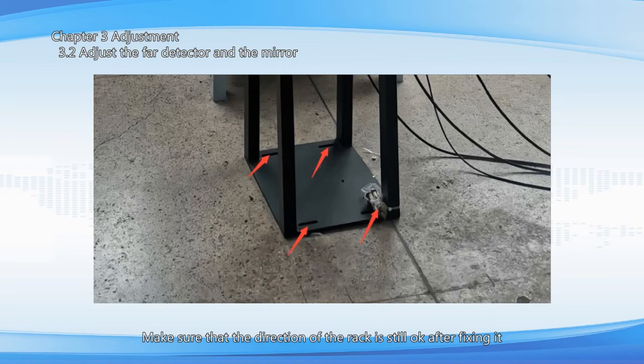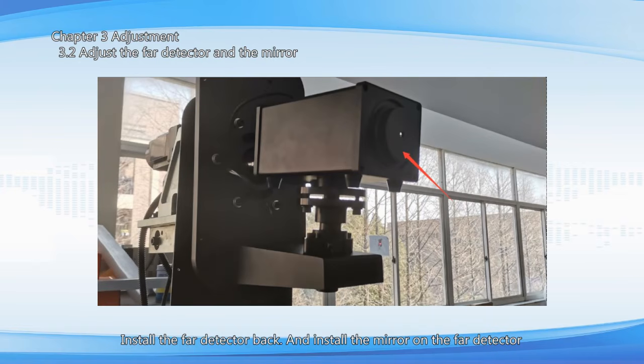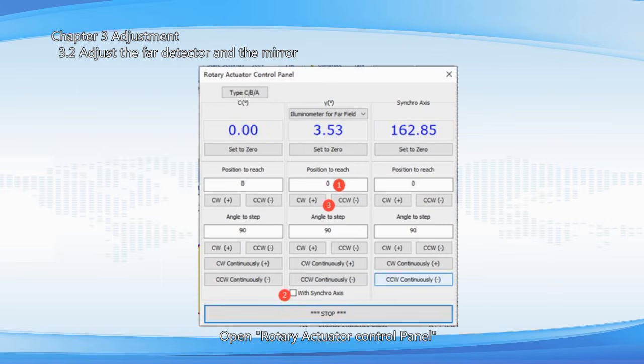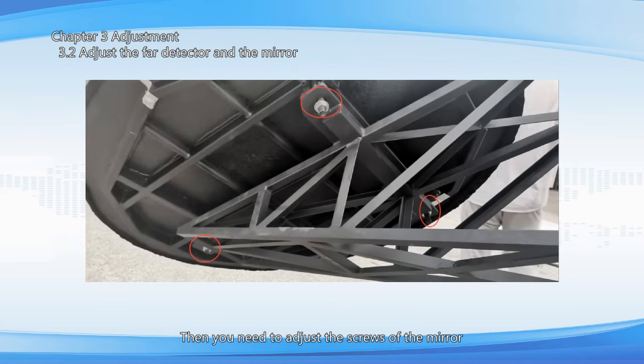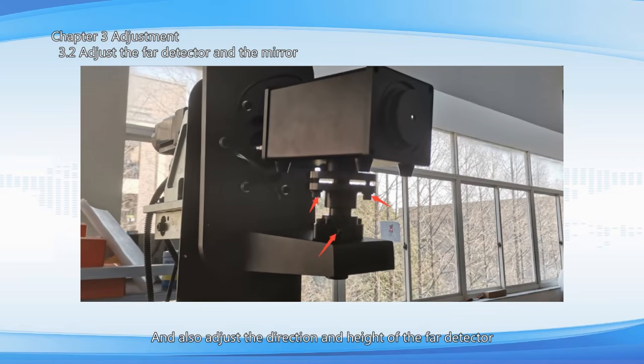Make sure that the direction of the rack is still okay after fixing it. Install the FAR detector back, and install the mirror on the FAR detector. Open rotary actuator control panel. Select illuminometer for FAR field. Input 0 here. Check with synchro axis. Then click to rotate the gamma angle and the FAR detector both back to 0° position. Then you need to adjust the screws of the mirror, and also adjust the direction and height of the FAR detector.